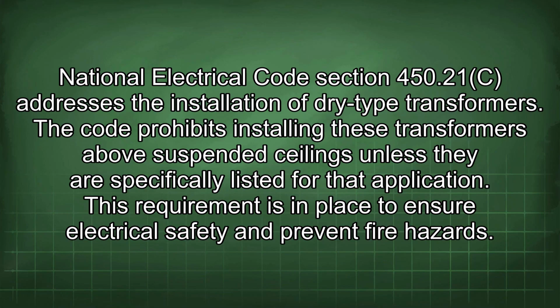National Electrical Code Section 450.21c addresses the installation of dry-type transformers. The code prohibits installing these transformers above suspended ceilings unless they are specifically listed for that application. This requirement is in place to ensure electrical safety and prevent fire hazards.